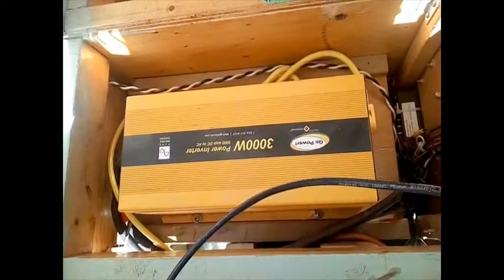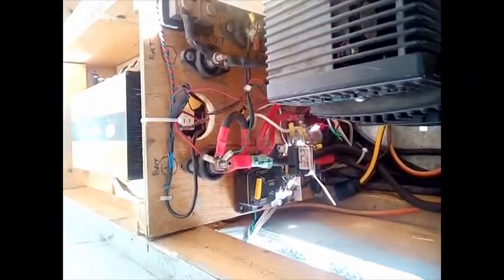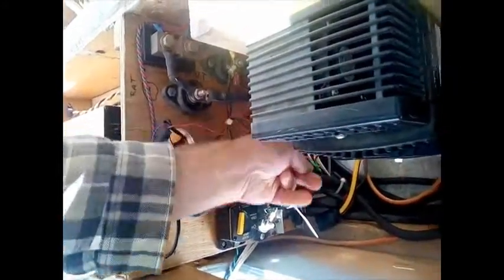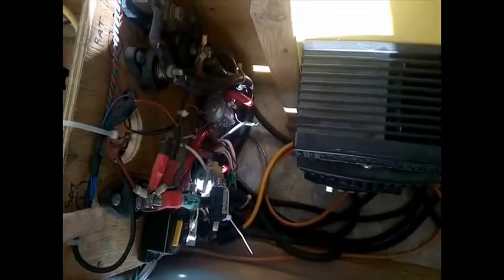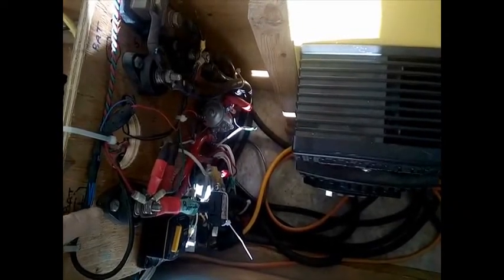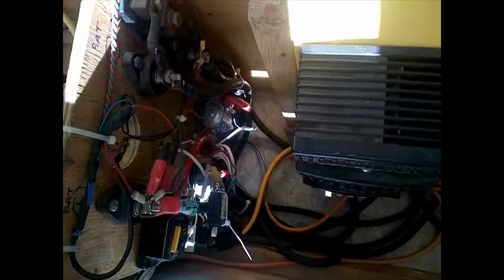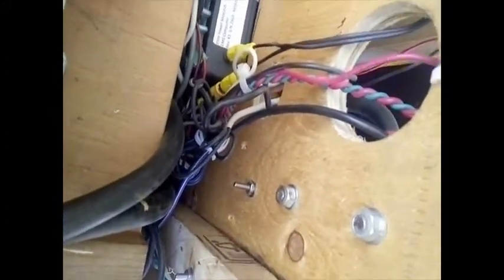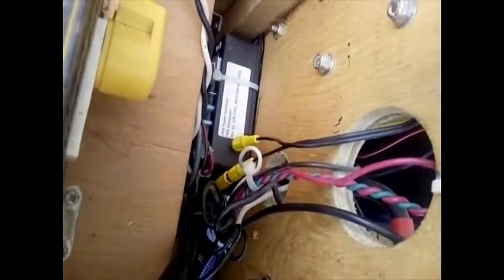With the electrical system, here is our sine wave inverter, a pure 60 hertz pure sine wave. Next we have the lithium-ion battery controller. Basically, there's a computer which measures temperature, voltage, and does balancing of the cells. The computer is located on the opposite side. And with it, it has connections for the disconnect solenoids, the data cable which speaks to all the bridges and takes measurements.